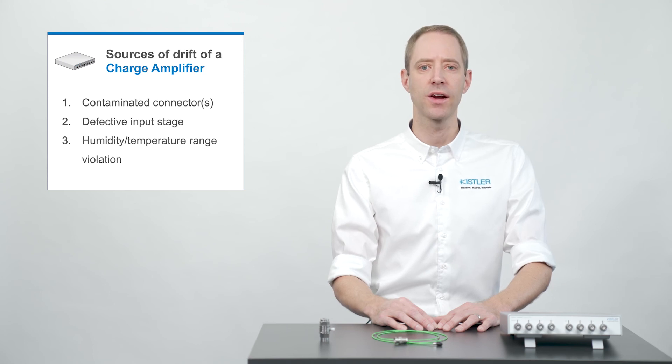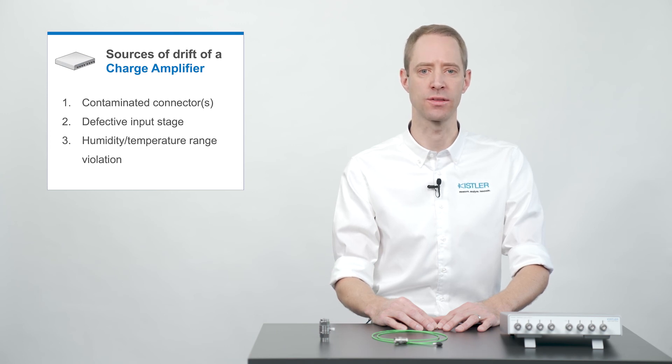For charge amplifiers in general, it is very important to stick to the specified temperature and humidity operating ranges. In case a device is operated outside the specified environmental conditions, moisture may condense inside the device and destroy the insulation sections.